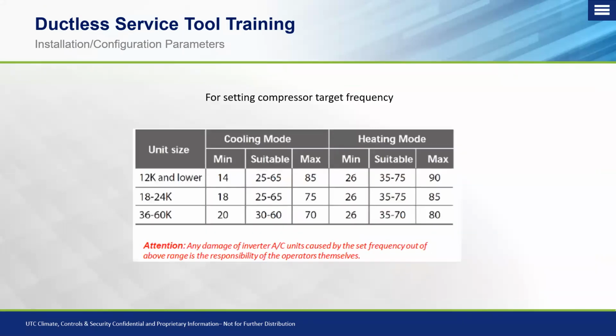Okay. And the most important part here, especially for setting the compressor target frequency, what we talked about in the beginning, is the sweet spot of the system. You'll see on here that cooling mode and heating mode have different minimums, maximums, and suitable ranges. So if for some odd reason you change something in the cooling mode to maximum or above, or the minimum or below, that is on you for changing that. And again, that's why I mentioned at the beginning of this, typically I haven't run into a situation where adjusting the target frequency of the compressor was necessary.